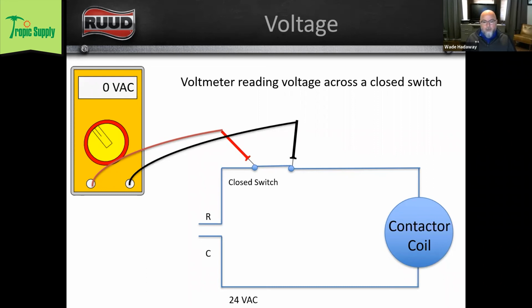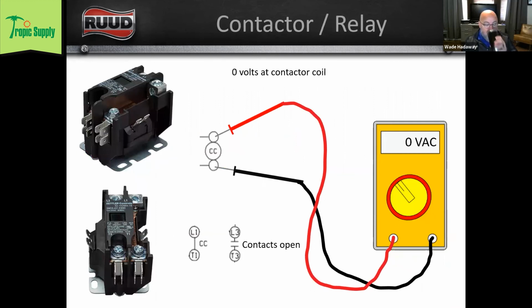A lot of times what people will do is they will read voltage in their thermostat, and they'll read from 2 terminals in their thermostat and think 24 volts means that switch is closed. It doesn't. It means that switch is open. 0 volts across a closed switch. You read voltage across an open switch. Which brings us to our contactor / relay, right?